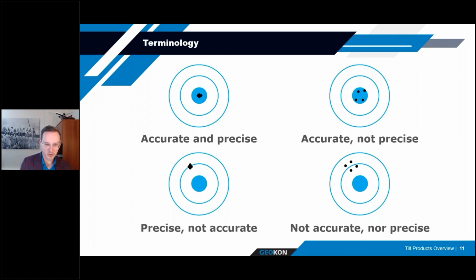across different reading intervals. So the next one going down is precise but not accurate, and I would say this is perhaps where the typical MEMS sensors would fall, where the actual angle of tilt may not be as accurate as it is precise. And a lot of times that doesn't matter because people are typically concerned with the change in tilt and not so much the absolute angle of tilt. And then you have the other two, accurate, not precise, and neither accurate nor precise.